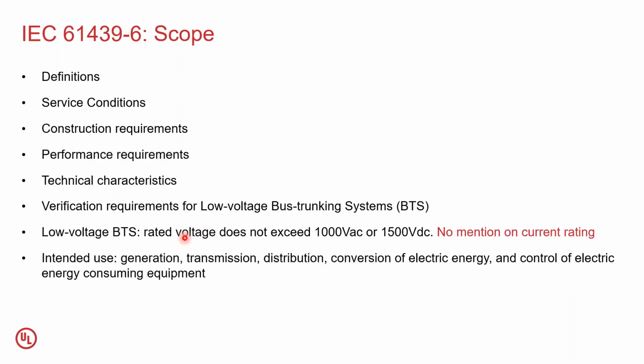The most important thing is the framework within which this standard talks. So any bus duct whose rated voltage does not exceed 1000 volts AC, nor exceed 1500 volts DC, can be covered under this standard, including all the accessories. For example, a busway with a plug-in system, elbow, joints, flanges, all the accessories related to the bus trunking system could be covered under this standard. Note that there is no mention of current rating, which essentially means that you can design as much as possible depending on the need. We have seen busways as high as 6000 amperes, sometimes going up to 7000 amperes, and also very small ratings, maybe a few hundred amperes. So there is no limitation on the current capacity as long as you are able to design the bus bars to this requirement.